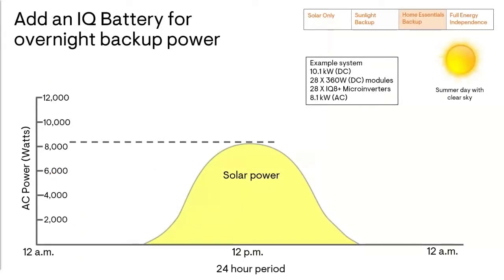The option to add a small battery to a relatively large solar system is pretty unique among options on the market. Typically, manufacturers limit the power of the solar system to be about 50% above the battery to ensure that the solar system doesn't essentially overwhelm and cause a collapse of the microgrid.